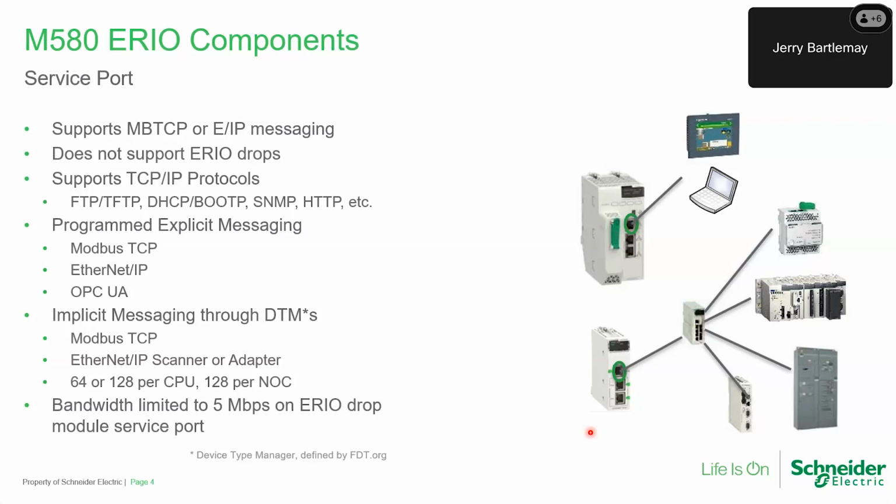So in an NOC module, the communications module, it's 128 transactions. Part of those are reserved for the EtherNet/IP adapter, what we call local slave there. And on the CPU, if it has remote I/O capability, it's a total of 64 transactions, or 128 if it does not have remote I/O capability. Because we have models that either do or do not have remote I/O in the M580.